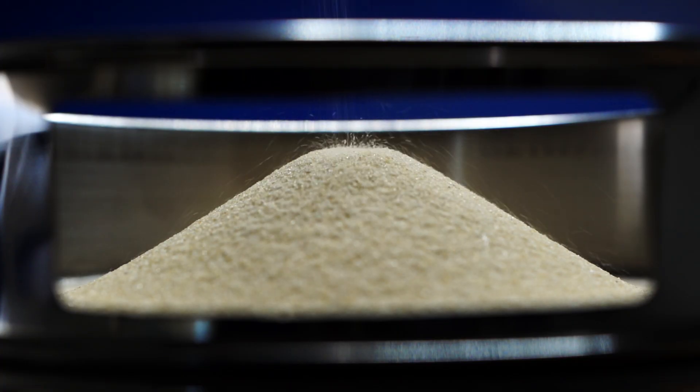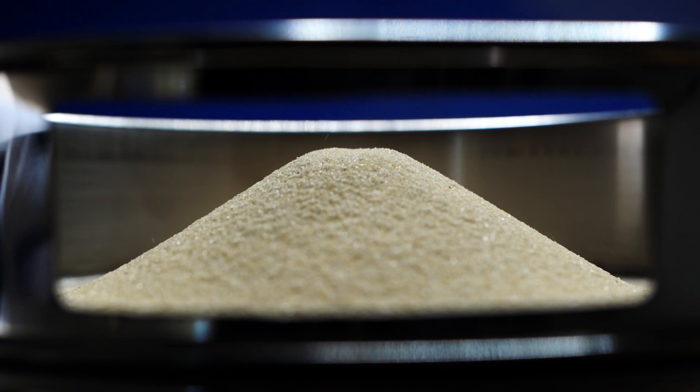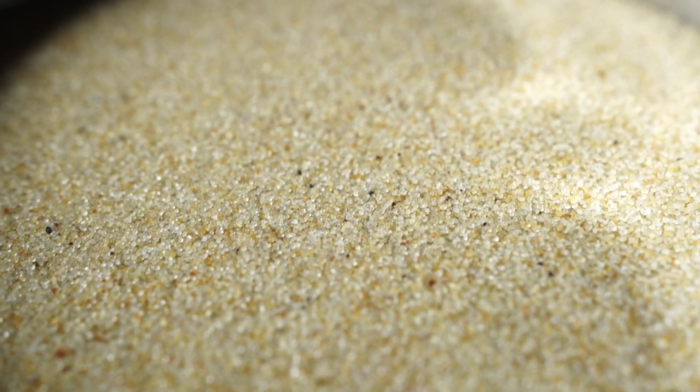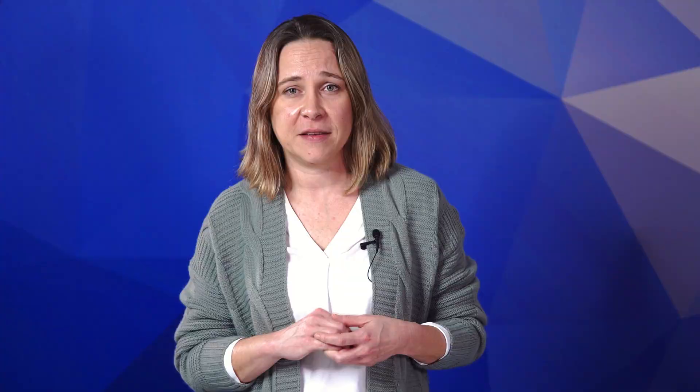The way you record particle size is different depending on which standards you're following. For example, in most ASTM standards, particles are measured based on the mesh count of the sieve that prevents the particle from falling into the next sieve in the stack. So if you're working with an aggregate and a particular piece of sediment was resting on a 50 mesh test sieve at the conclusion of the analysis, you would describe that particle as a 50 mesh piece of sediment. Particles are also measured in inches, millimeters, and microns. A good rule of thumb is that if a particle is smaller than an inch, use the mesh count, millimeter length, or micron size as the unit of measure.